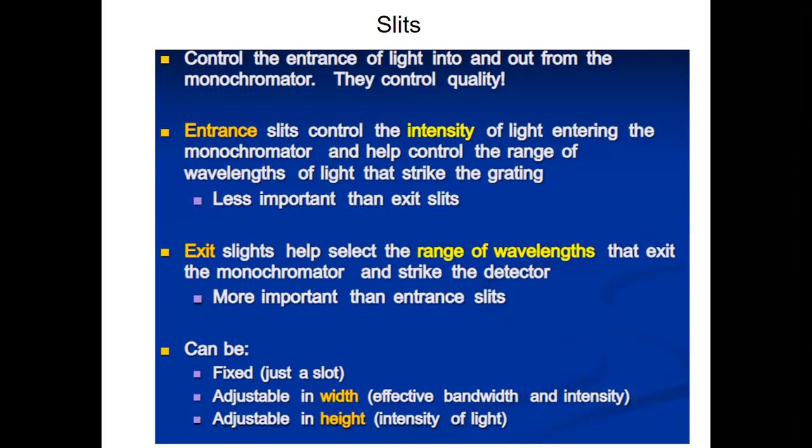It is said that the entrance slit is less important than the exit slit. Whatever wavelength range comes to the grating, we can select the particular wavelength range we are interested in. Therefore the entrance slit is also important, but compared to the exit slit, it is less important, right?